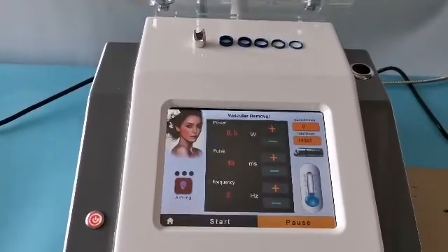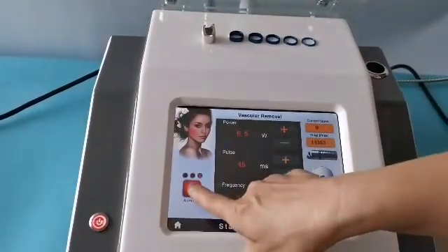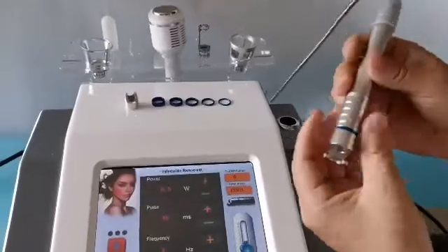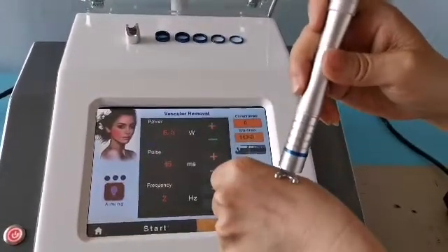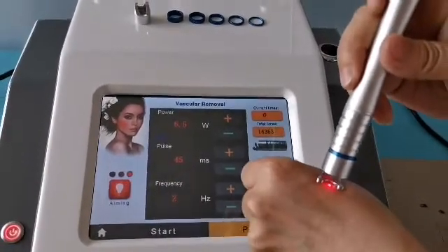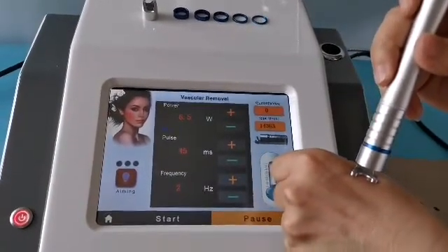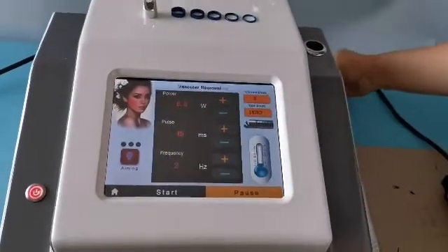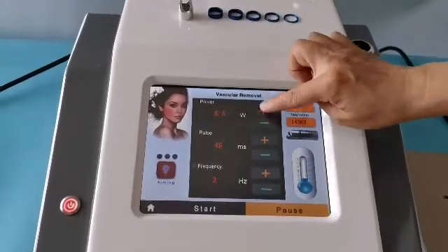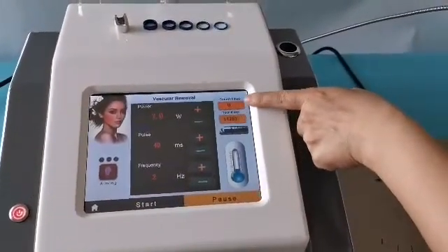Other parameters are simpler. This light bulb is the aiming light. Click this button to adjust the aiming brightness: one is weak, the second is brighter, and the third is particularly bright. Generally, the first level can see the red blood silk, but it is not clear when it is too bright. Here is the number of laser outputs since this boot up. Here is the total number of laser outputs from this instrument.